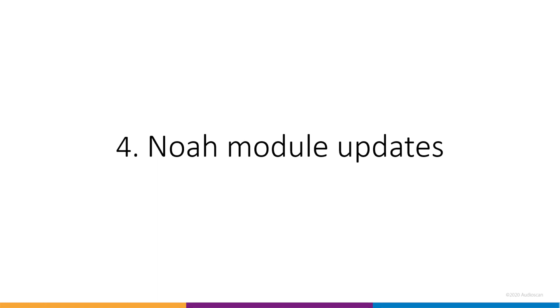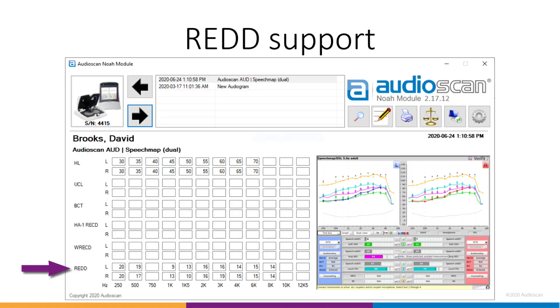Four, Noah module updates. The Noah module has had two small updates this time around. The first is no surprise. The Noah module now supports REDD data measured on the Verifit 2. REDD data can be viewed on screen, printed, or later sent back to the Verifit for subsequent testing.